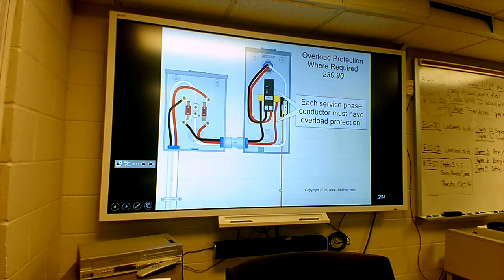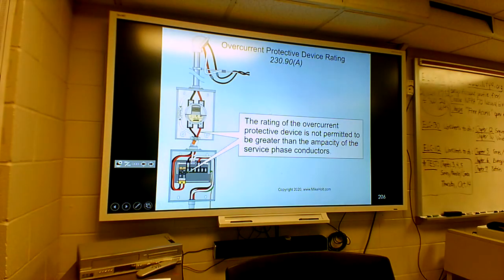But coming in from the meter base there, here you've got a disconnecting means before it goes into the house. And that's for both of your phase conductors. The neutral doesn't go through a breaker, or the ground. It's just the hot wires. And the rating of that device cannot be greater than the amp rating of the conductors.